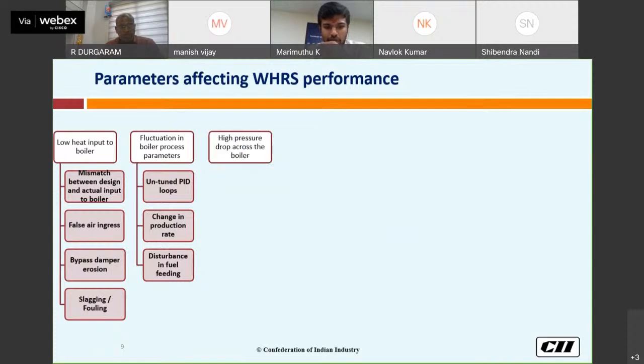Next is high pressure drop across the boiler. Generally high pressure drop occurs if there is any disturbance in the flue gas path system. For example, if fouling and slagging is there, or any additive dust in the cooler dust, that will also cause fouling. Then high pressure drop will occur.